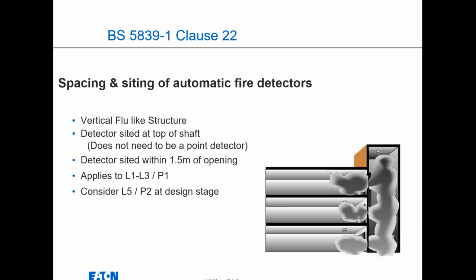So vertical flue-like structures: you should have a detector at the top of the shaft, whether that's a riser or a lift shaft, and that should be within 1.5 meters of the opening on each floor as well. That applies to L1 to L3 and any P1 designs, and again L5 and P2 you can consider if you're doing that at design stage.